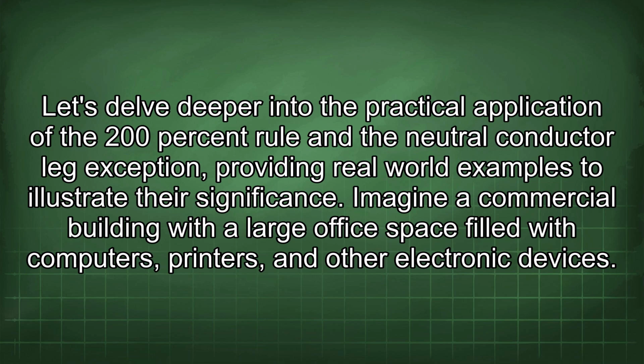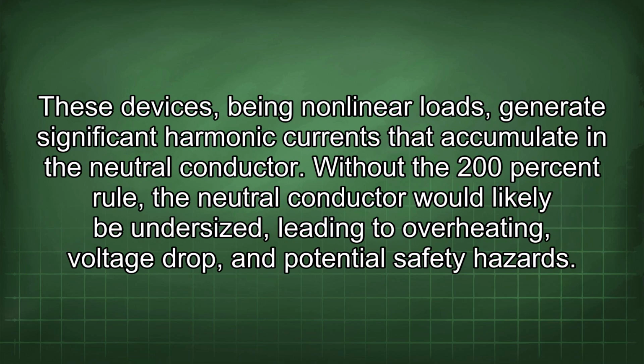Imagine a commercial building with a large office space filled with computers, printers, and other electronic devices. These devices, being nonlinear loads, generate significant harmonic currents that accumulate in the neutral conductor. Without the 200% rule, the neutral conductor would likely be undersized, leading to overheating, voltage drop, and potential safety hazards.